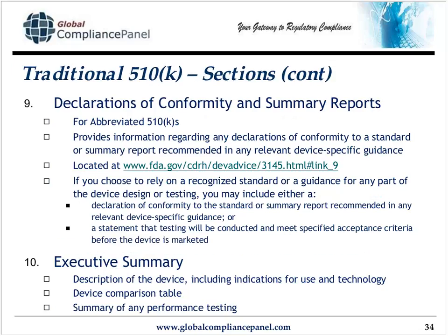Section 9 is the declaration of conformity and the summary reports. This is limited to abbreviated 510Ks, and it references any declarations of conformity upon which you're going to rely in your submission.